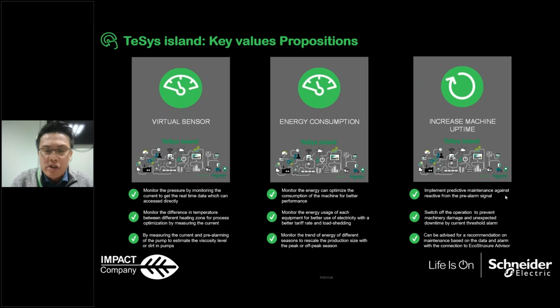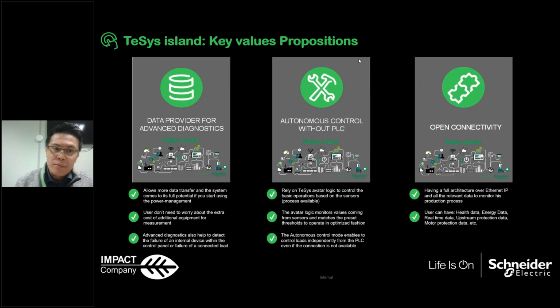So this is what we call increasing the machine uptime, because you can understand what is happening before the failure. And then it's also a data provider for the advanced diagnostics. So it allows more data transfer, and the system comes to its full potential if you start to use the power management. So we have all the data, we provide the data. With this data, you can have an analysis of what is happening in the system. And then the user doesn't need to worry about the extra cost for additional equipment for measurements, because with the TeSys Island, with this smart motor management system, all the data is already available. No need to consider additional equipment, such as power meters or other equipment, to get the data. And the advanced diagnostics function also helps to detect the failure of the internal device. So we will have different comparisons, for example, maybe the flow of the water is too high, and then the current is too high, and then you can identify what's happening in the system.